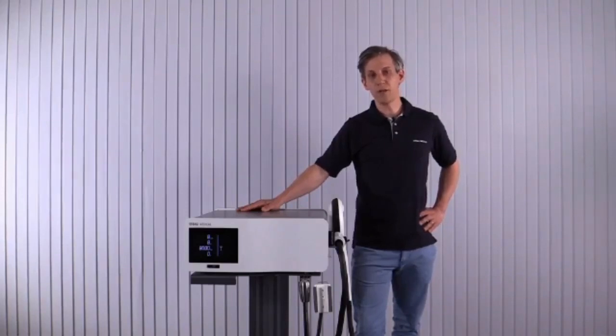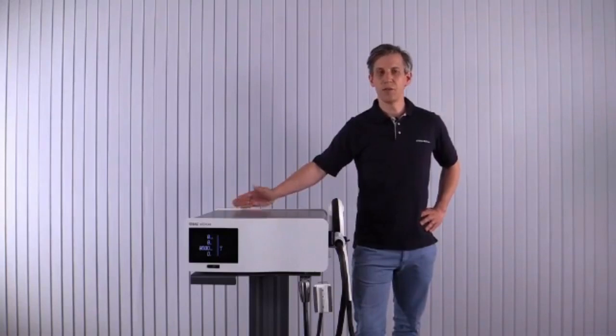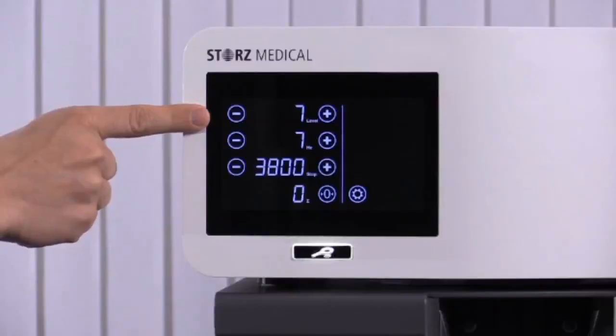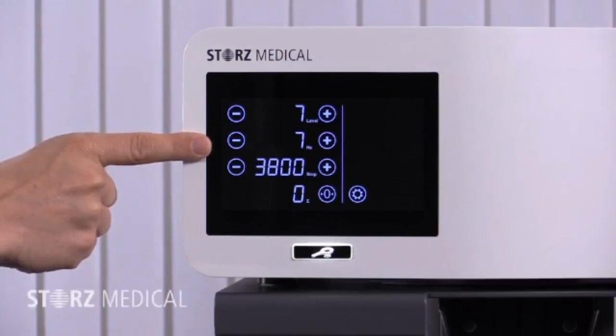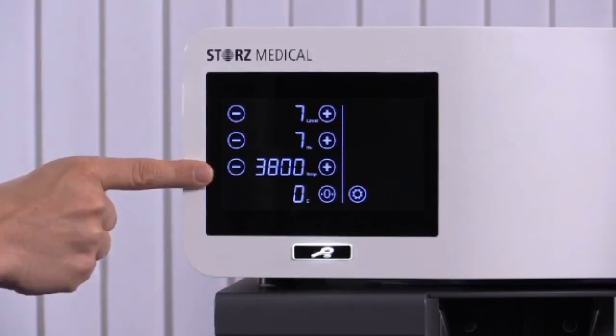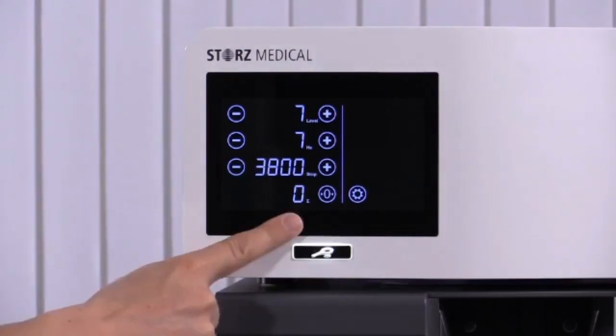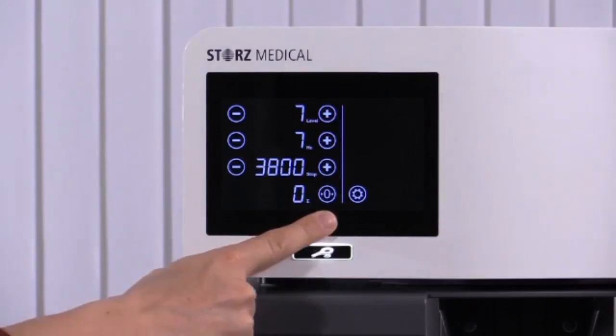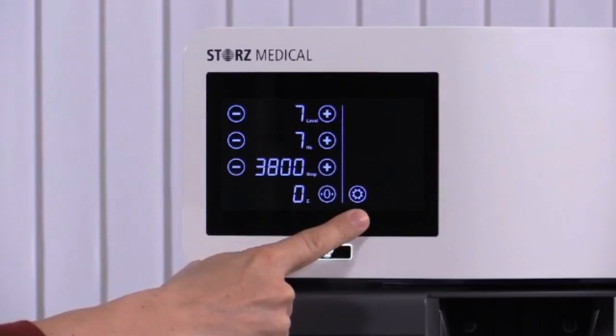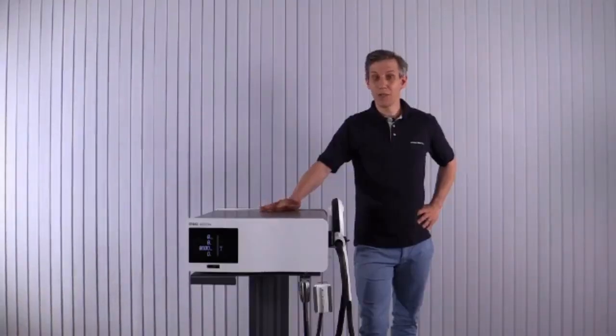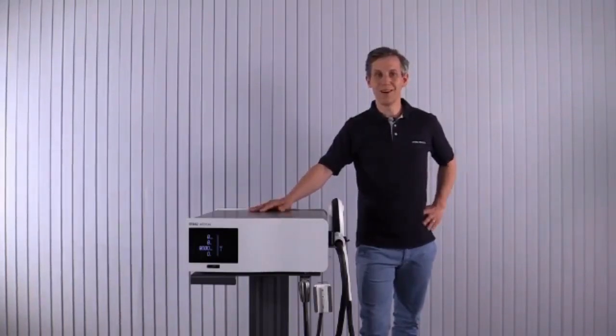Now let me explain the core functions of the user interface to define treatment parameters. You can set the energy level in 6 steps, from level 3 to level 8. In the second row, adjust the frequency of the pulses from 1 Hz to 10 Hz, where 10 Hz equals 10 pulses per second. In the third row, define the maximum pulses per treatment, adjustable while treating the patient. On the bottom left is the pulse counter, in the middle the reset button, and on the right the operating menu, which contains system information and further settings. Now, with the parameters set, you can proceed with the actual treatment. Thank you for watching, and hopefully see you soon.